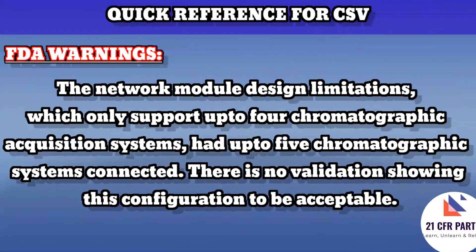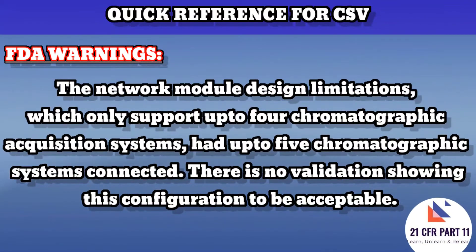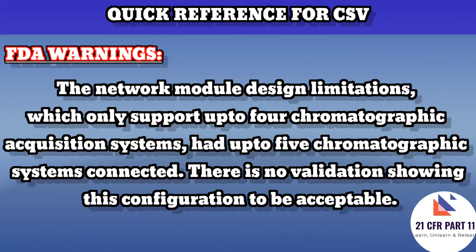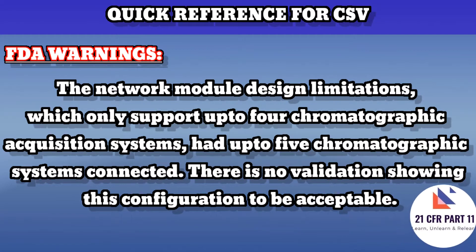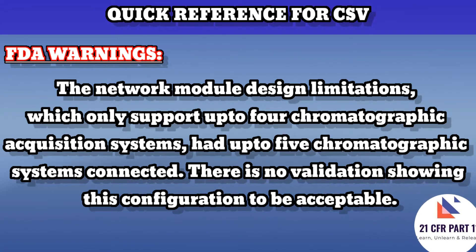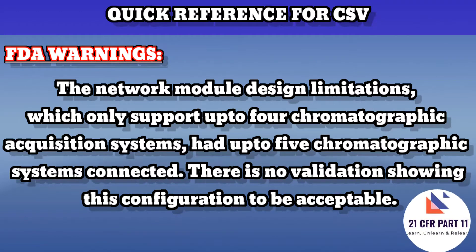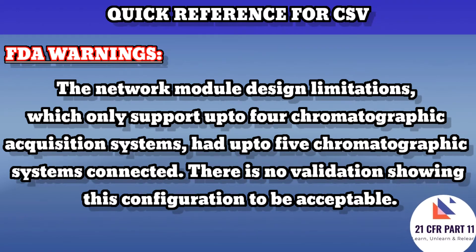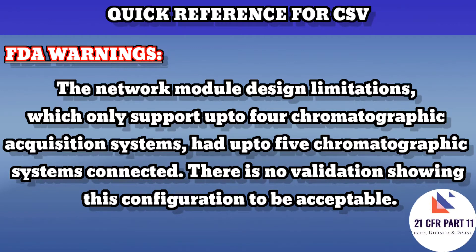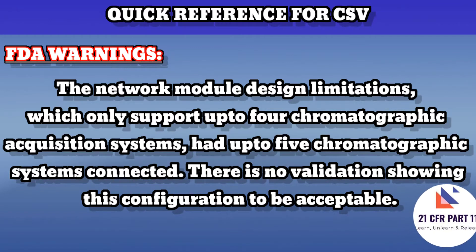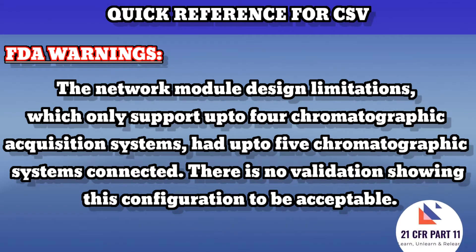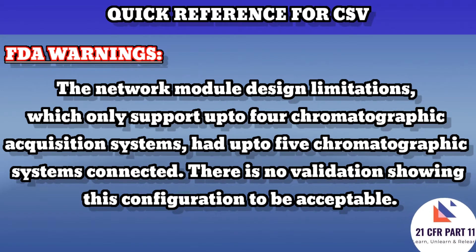Now let us see some FDA warnings. The first warning says that the network module design limitations which only support up to four chromatographic acquisition systems had up to five chromatographic systems connected. There is no validation showing this configuration to be acceptable. This FDA warning is related purely to the network and the configuration settings.